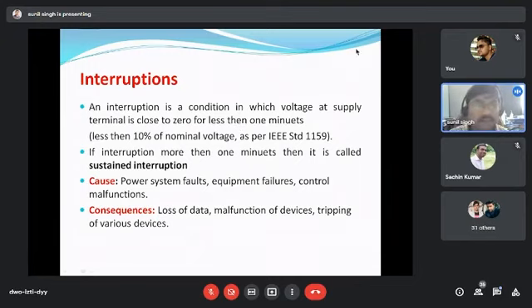Next are the interruptions. Interruptions are very well known from earlier. You might have experienced long-term interruptions. In villages there is a very good example of interruptions; they are very used to interruptions for a very long time, meaning longer than 12 hours. An interruption is a condition in which the voltage at the supply terminal is close to zero, meaning it is almost zero.